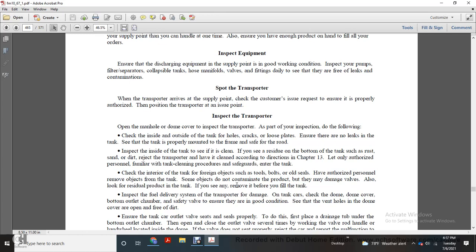Check the interior of the tank for foreign objects such as tools and old seals. Have authorized personnel remove the objects. If the objects do not contaminate the product but may damage the valves, they must also be removed. Look for residual product in the tank; if present, remove it before you fill the tank.